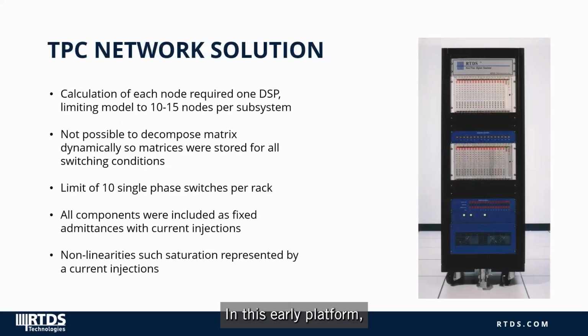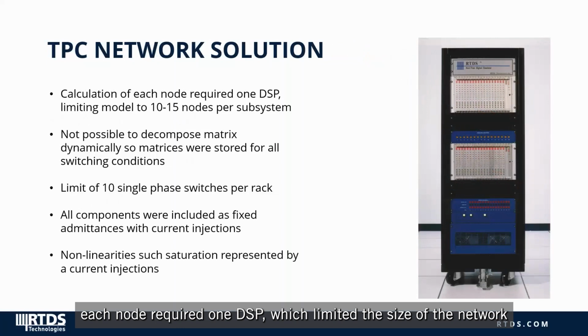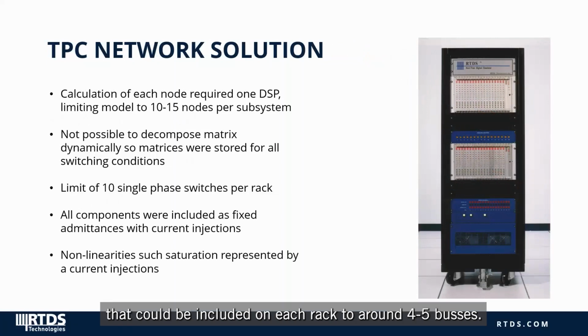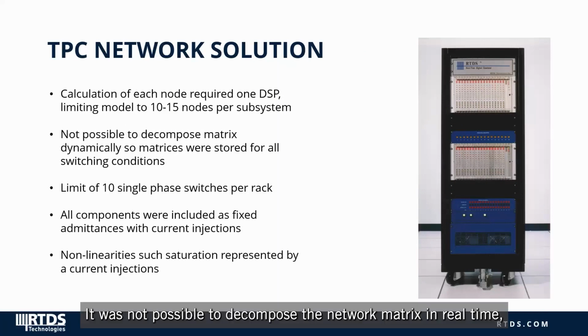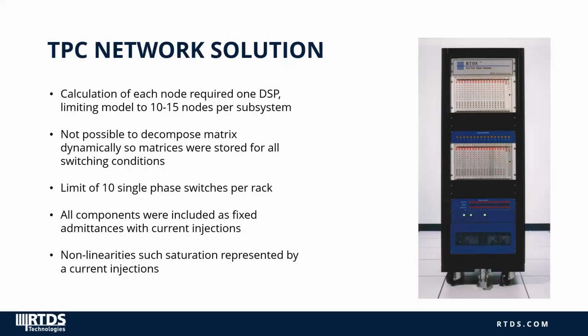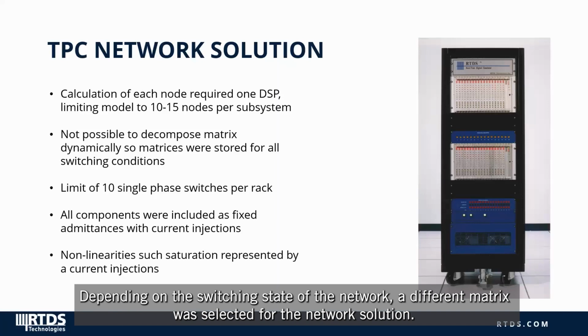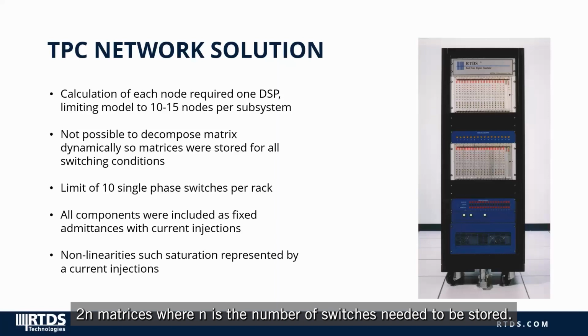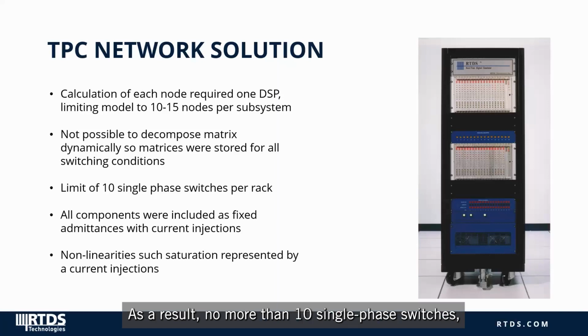In this early platform, each node required one DSP, which limited the size of the network that could be included on each rack to around 4 to 5 buses. It was not possible to decompose the network matrix in real time, so different matrices were stored to represent each switching state. Depending on the switching state of the network, a different matrix was selected for the network solution. 2 to the n matrices, where n is the number of switches, needed to be stored. As a result, no more than 10 single-phase switches, breakers, and faults were permitted per rack.